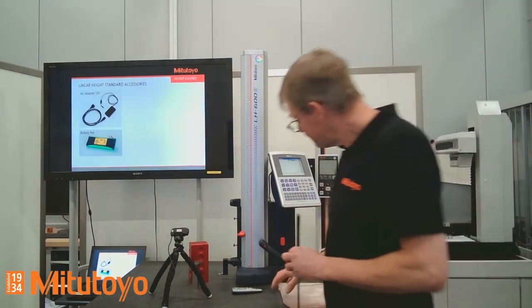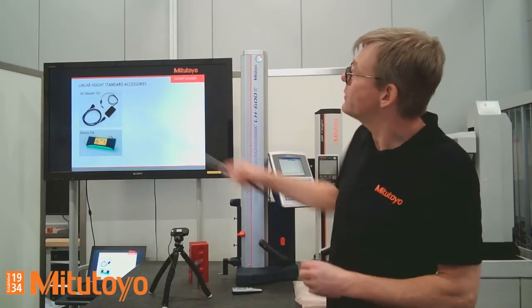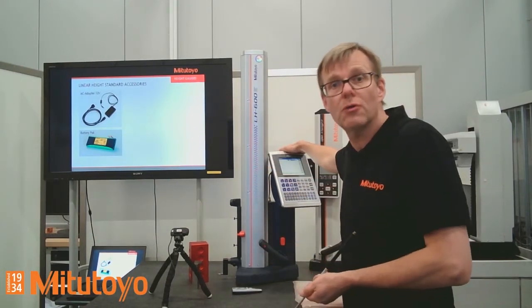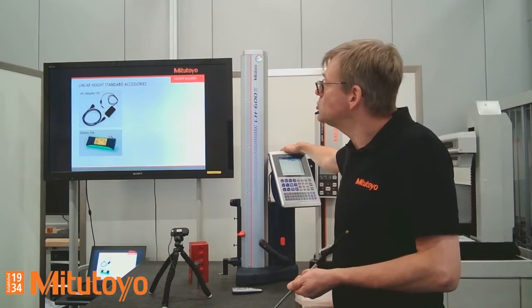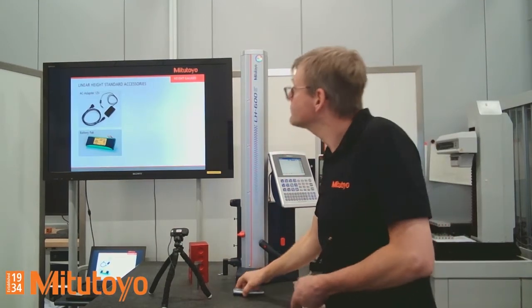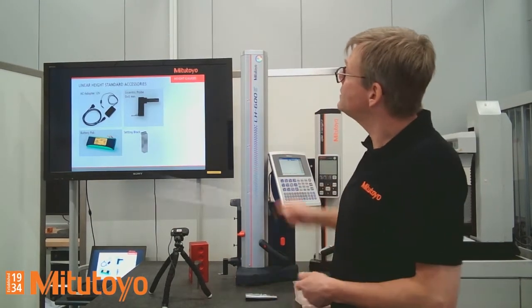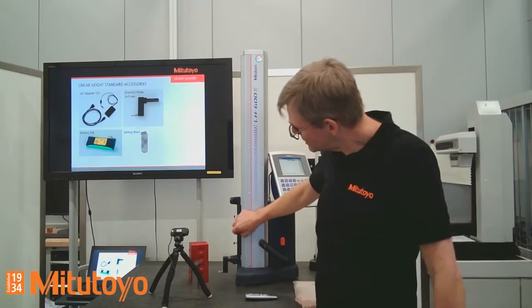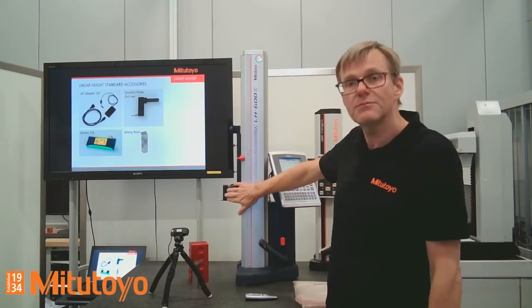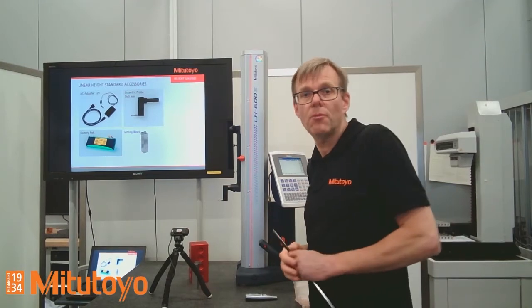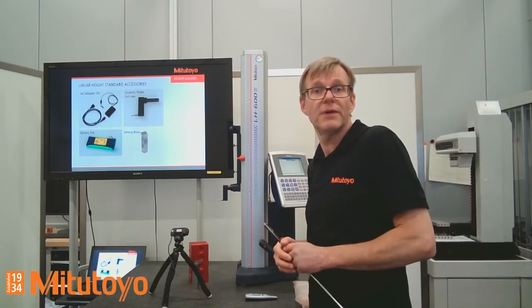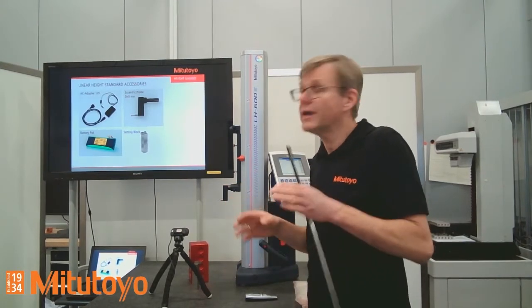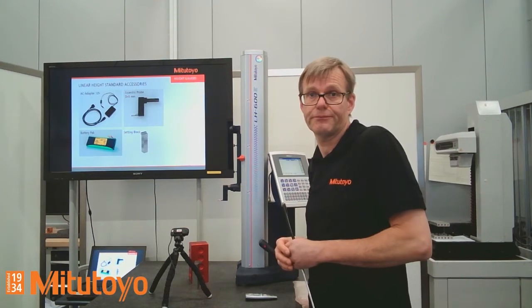Then, for sure, we have the integrated accu pack. It's integrated in the controller box, so there is no need to show this in detail. Furthermore, we have the eccentric probe, which you can see already integrated in the machine. This standard probe has a diameter of 5 millimeter, and usually around 70-80% of the measurement tasks you can use this one.